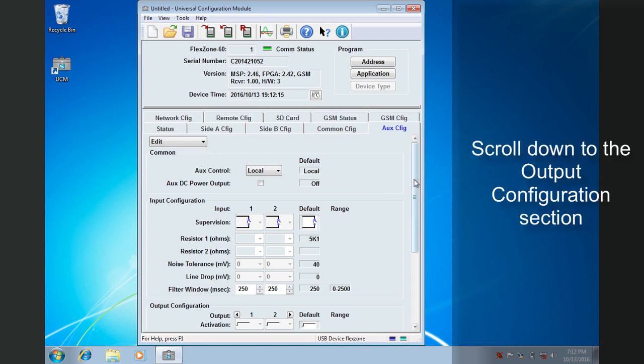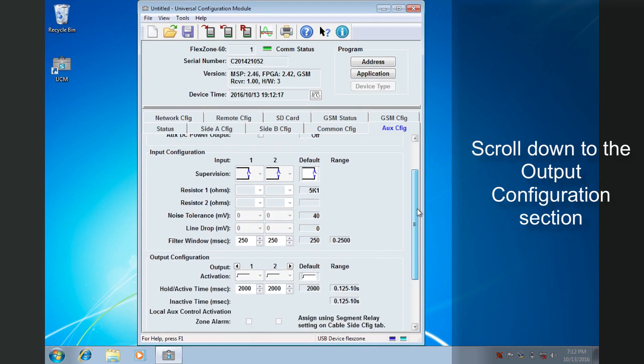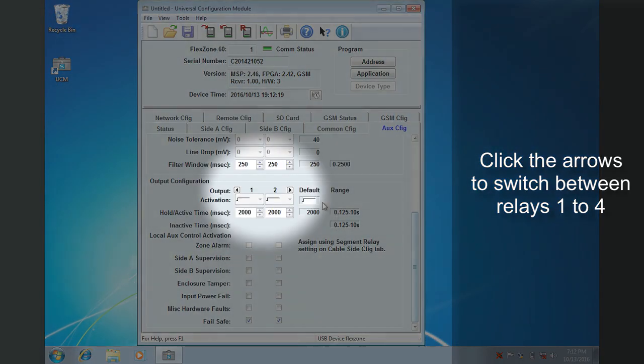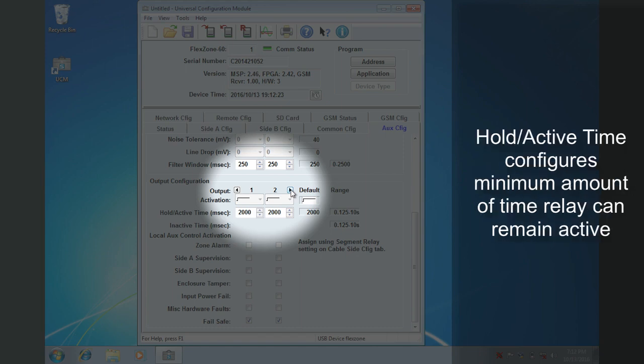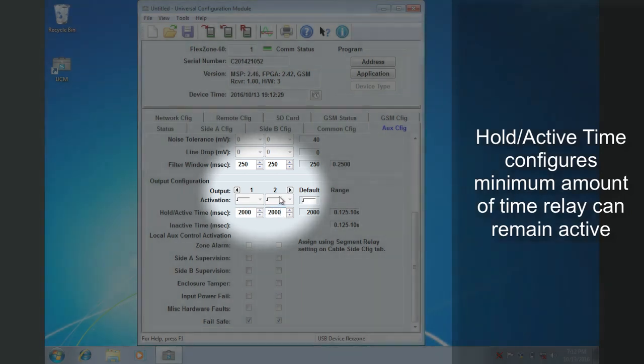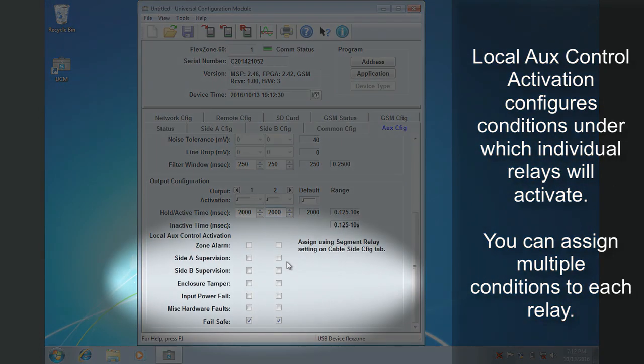Scroll down to the Output Configuration section. By default, the configuration for relays 1 and 2 are shown. Click the arrows to switch between relays 1 to 4. In Local mode, the activation type is fixed. The relay will remain active for as long as the configured condition occurs, or for the hold active time in milliseconds, whichever is longer.